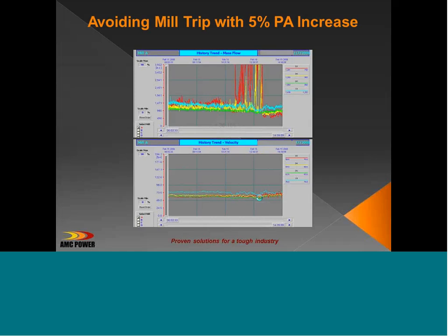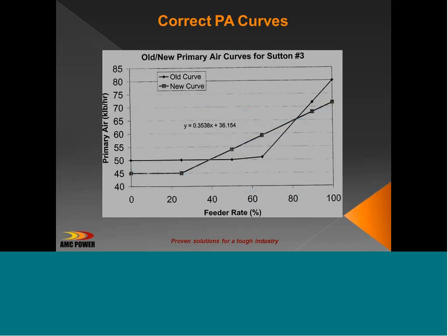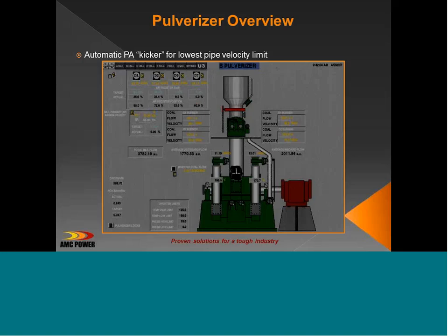So 2 things. The power plant decided to have engineering redo its PA curves. By looking at the fuel flow through the entire load range, they could determine when the velocities were getting low, to redo it so that they would have more stable coal velocities throughout the entire load range. But even in the event of wet coal or bad fineness because the mill is getting worn, they wanted to build a new control room screen, and I realize this is a little fuzzy.